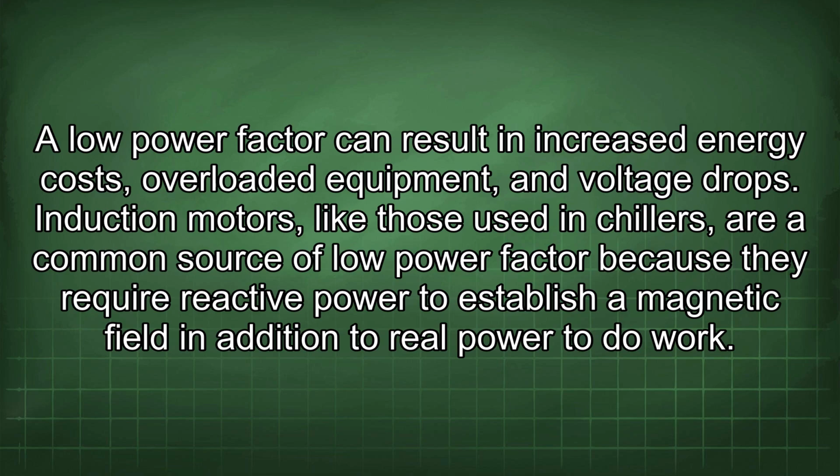Induction motors, like those used in chillers, are a common source of low power factor because they require reactive power to establish a magnetic field in addition to real power to do work.